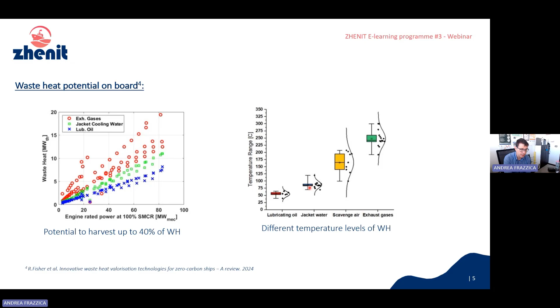While if you try to recover waste heat in the range, let's say around 100 degrees C, then you are recovering a waste heat stream that is usually not very efficient in terms of thermodynamic conversion. So our target was to try to work in the range from roughly 120 down to 50 or so. That is purely waste heat at this stage.